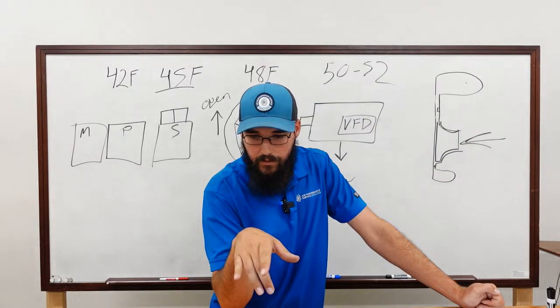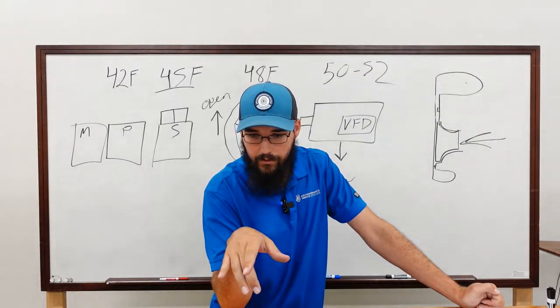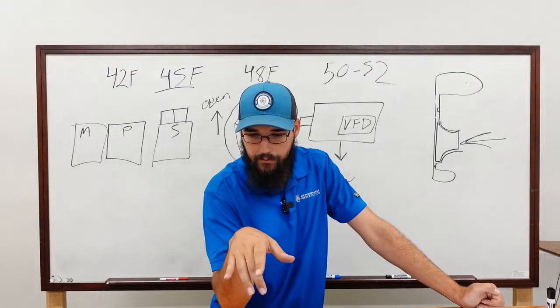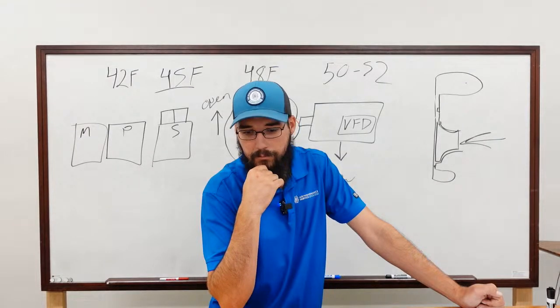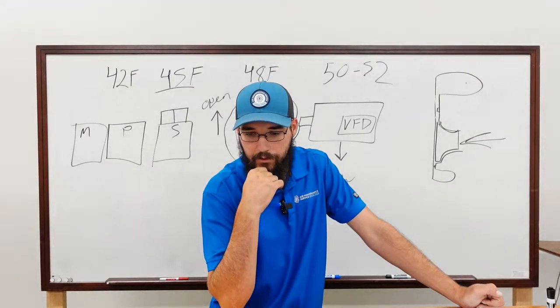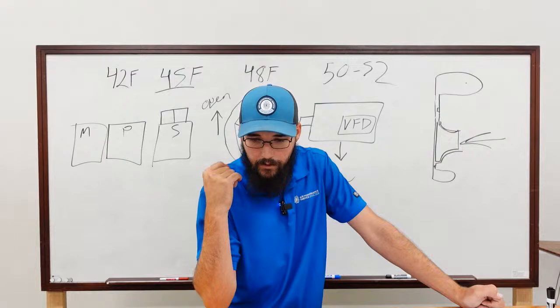I think Trane says a barrel can freeze and bust in under a minute when refrigerant migrates, which is essentially what's happening during charge and recovery. If you push pull all your liquid and get it all out before you switch to vapor, there's no chance of freezing.